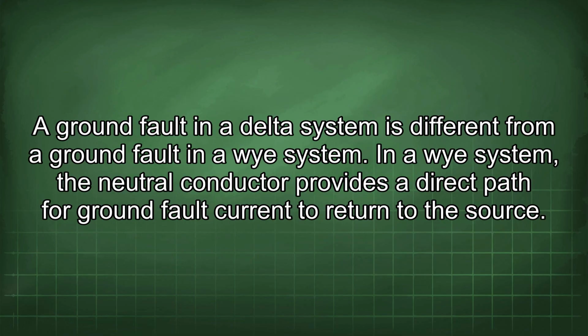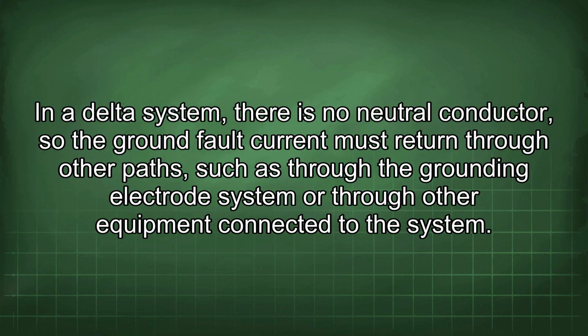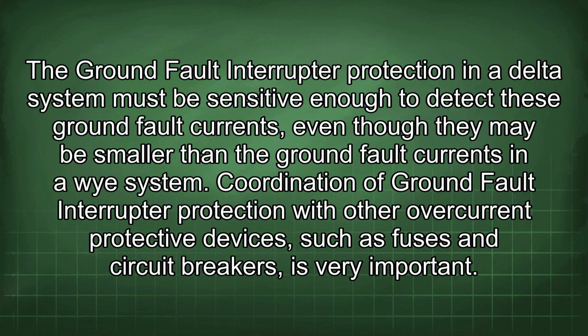A ground fault in a delta system is different from a ground fault in a Y system. In a Y system, the neutral conductor provides a direct path for ground fault current to return to the source. In a delta system, there is no neutral conductor, so the ground fault current must return through other paths, such as through the grounding electrode system or through other equipment connected to the system. The ground fault interrupter protection in a delta system must be sensitive enough to detect these ground fault currents, even though they may be smaller than the ground fault currents in a Y system.